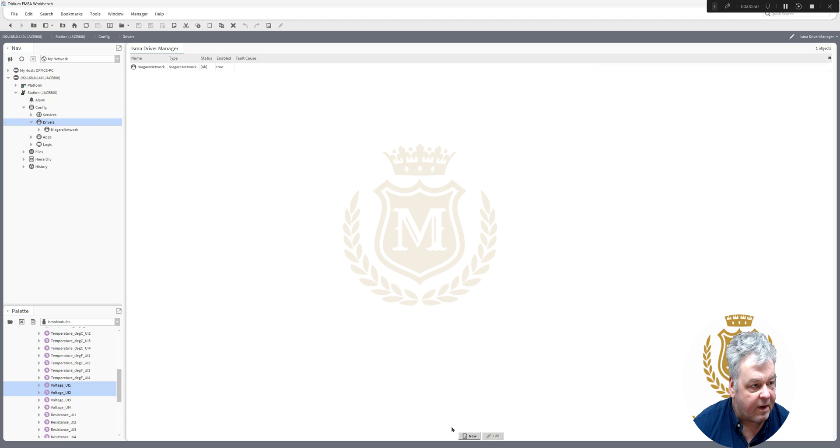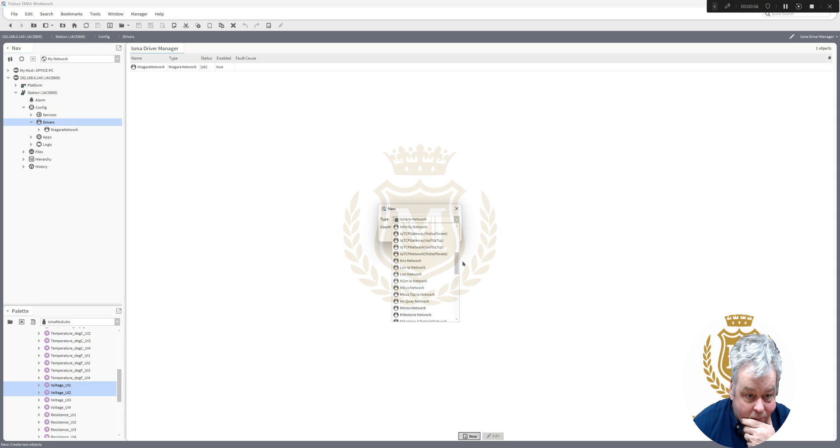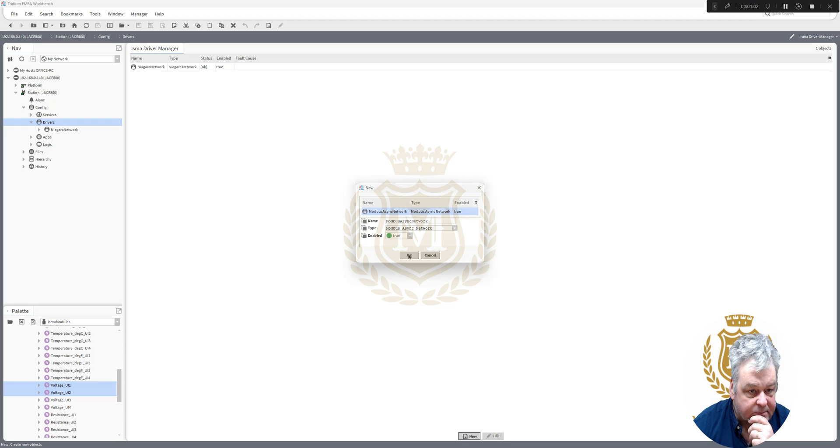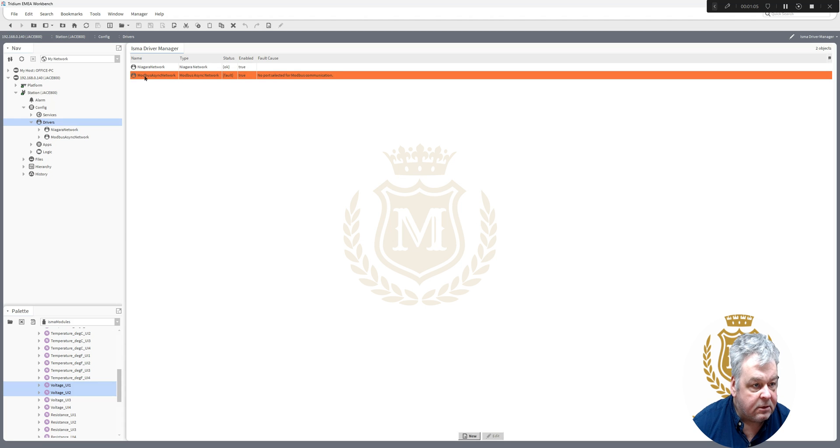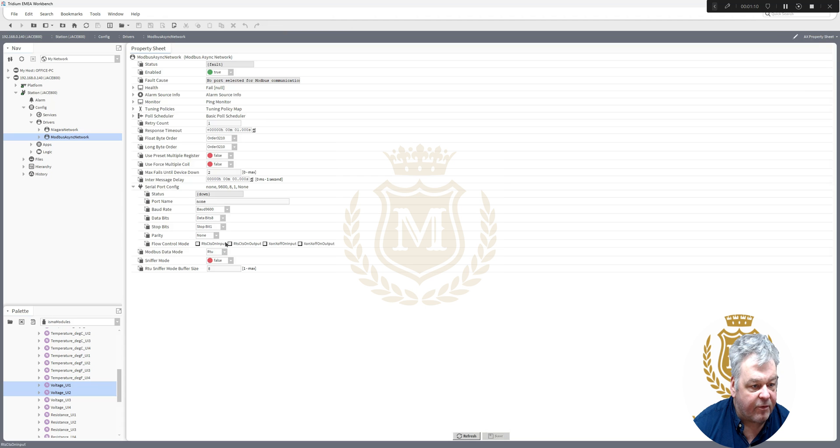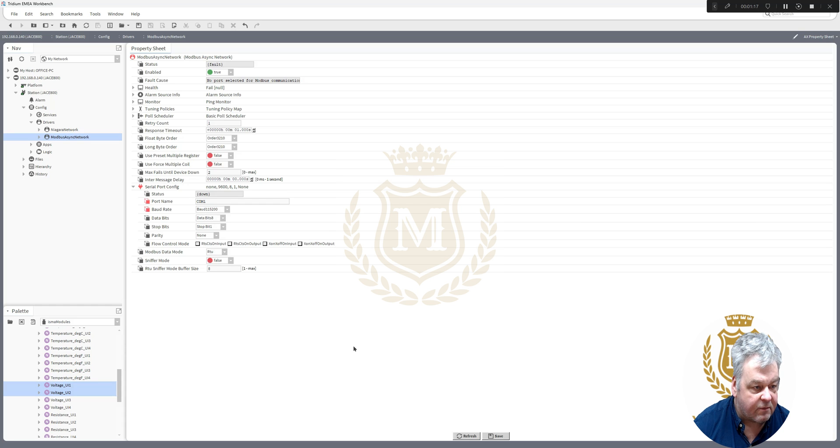We're now going to install that onto our Tridium Niagara controller. So I'm going to use Modbus network, Modbus async. That will do for me. And we've got to set the COM port for it. Views, AX Property Sheet, COM1, and we'll set it at the highest baud rate. Save that.